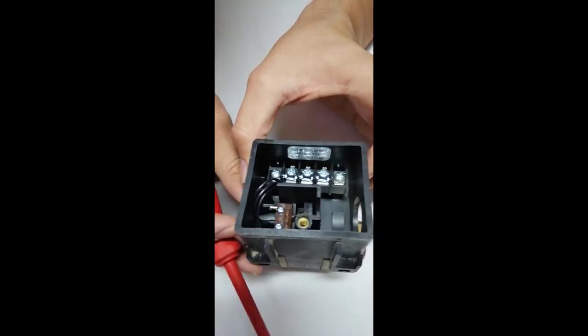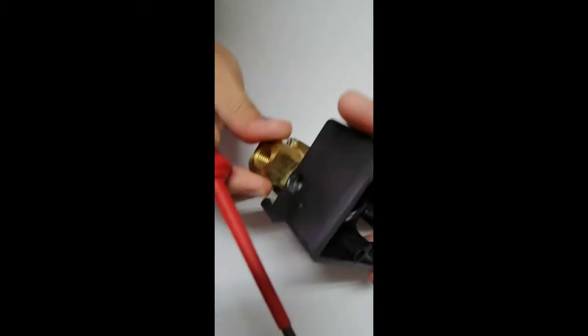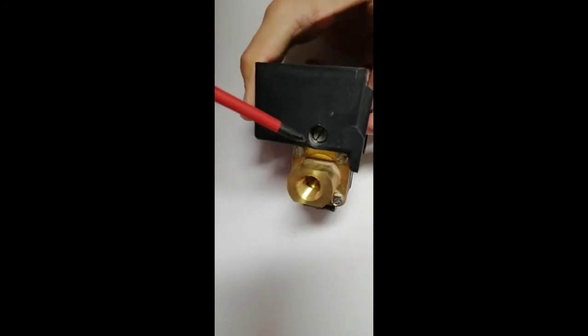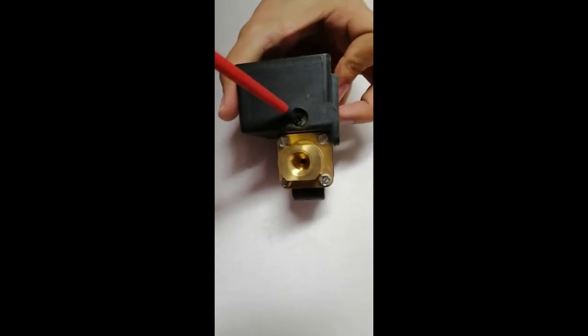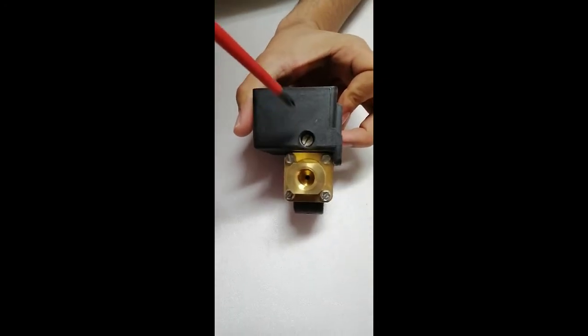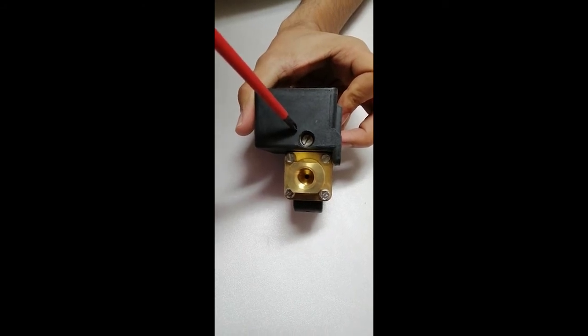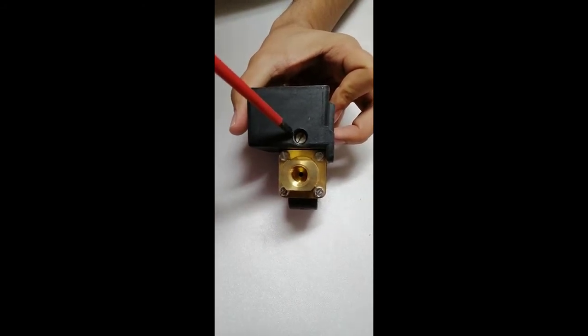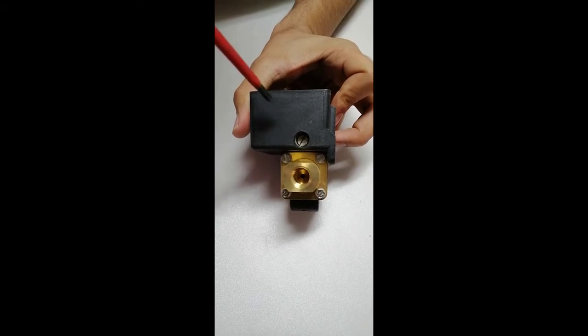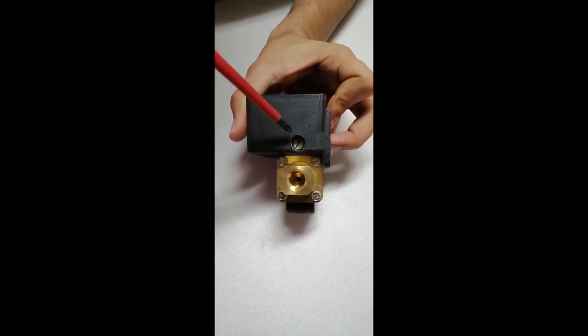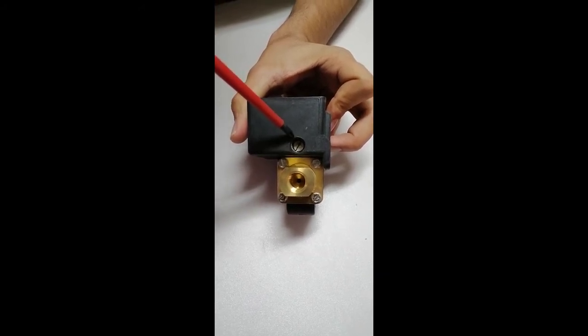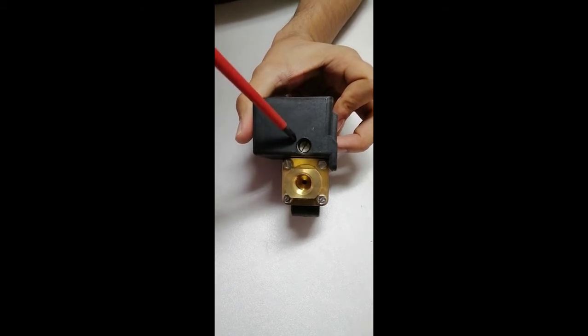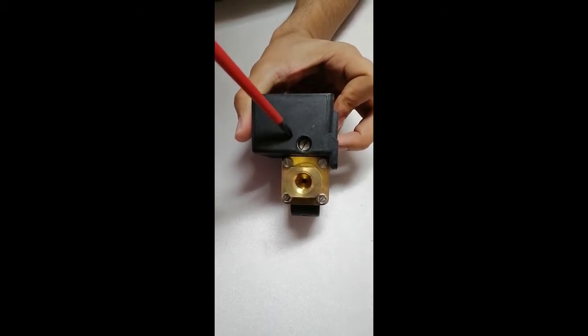Now to make adjustment about the set point, there is a screw given in here. So using this screw we can make adjustment or calibrate, we can adjust the set point for differential pressure switch. So this adjustment is usually done at the site when it is installed on the pump, and then we make this adjustment by using this screw. Okay, so this increases or decreases the sensitivity of this differential pressure switch.